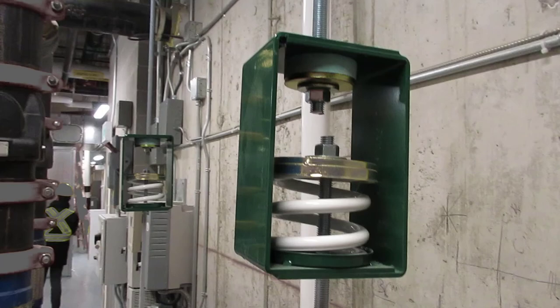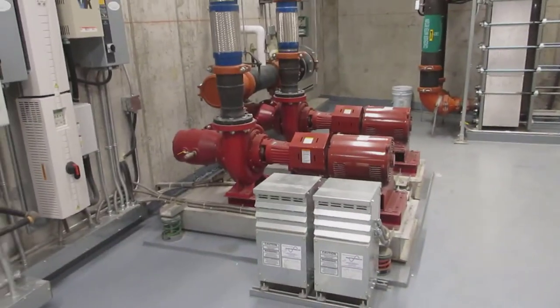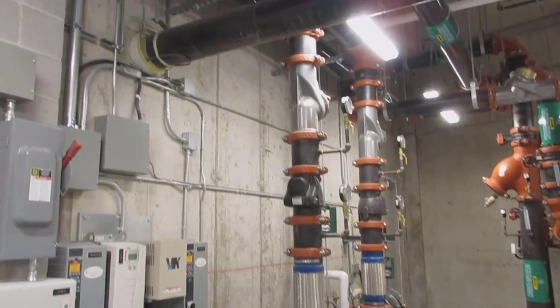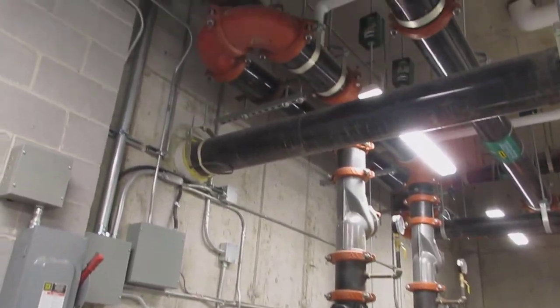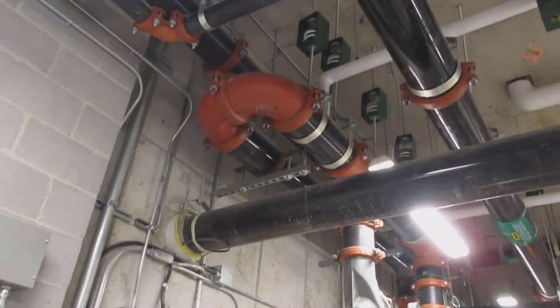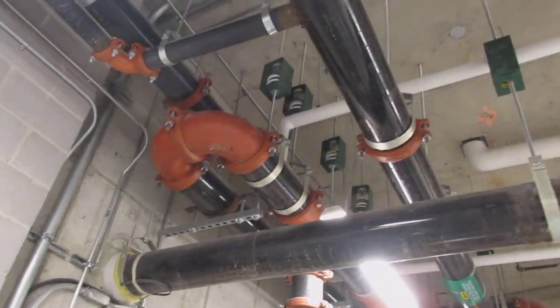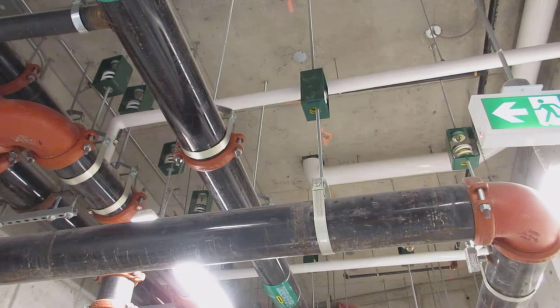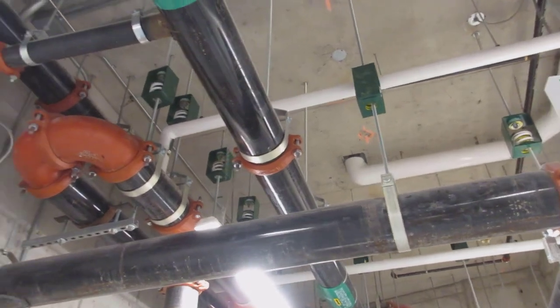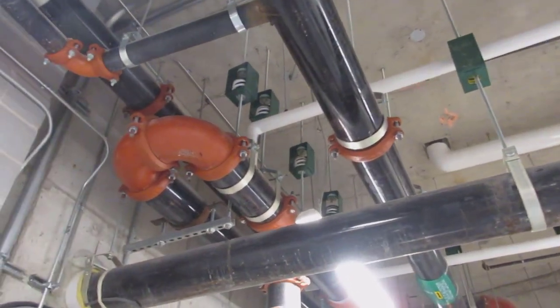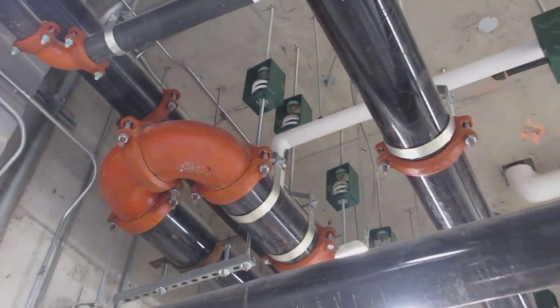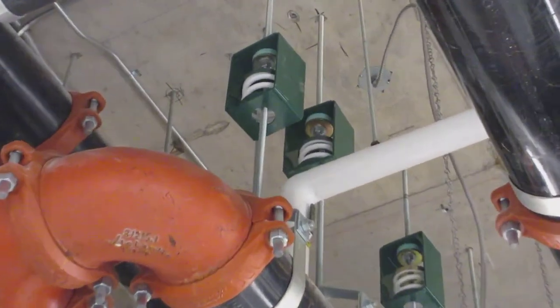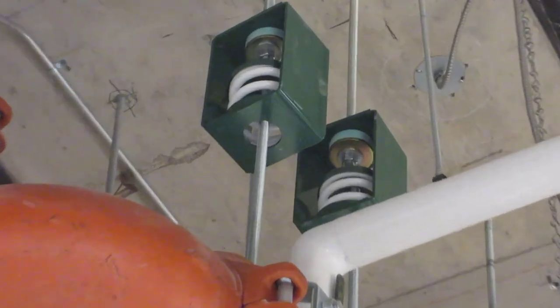We're going to walk around a few other pumps on this job and look at the spring hangers overhead and see what we can see. We'll start with the same condenser water pumps we were just looking at, but now we'll look at the discharge pipe header up high. There are quite a few hangers up there and it can be difficult to inspect from below, but one thing we can do is look for rod misalignment. Does the lower rod touch the side of the hanger box hole?